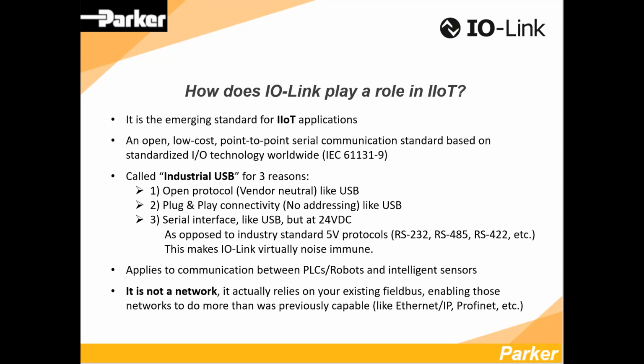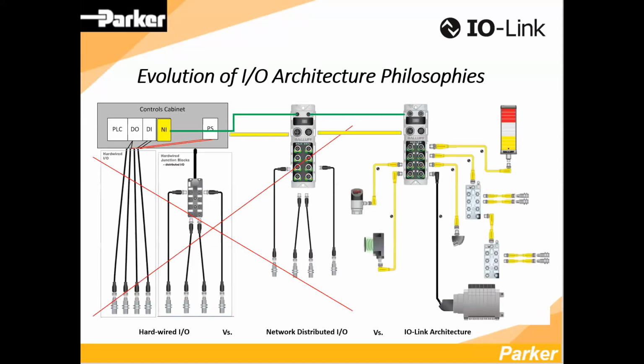And we already talked about the fact that it's not a network. This goes through a little bit of evolution, thinking about connectivity: from hardwiring sensors back into a panel through a cord grip or bulkhead to a terminal strip, on up to an IO card in a PLC or robot enclosure, then basically getting replaced with distributed or networked IO, where you're plugging sensors into a field bus module directly connected to the field bus. Then you get to IOLink.